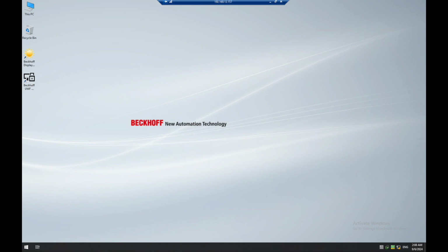And on the Siemens environment, it's part of, I think, TIA Portal 14 or 15, where once you have the right firmware, the OPC server directly resides on it. There's not much you need to do, and you're able to expose the relevant tags to Ignition, and then you can connect those and add it to your HMI or SCADA. For Beckhoff, it's a little bit different. You need to follow a couple more steps, and obviously you need a license to run OPC. So let's do that. Let's go.